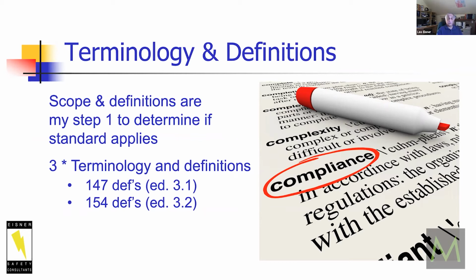But I always go to the scope and I read it and try to understand, does my product fit in the scope of the standard? ISO makes it hard because you can't tell a definition from any other word, because they're all in small letters. There's no small caps. IEC, at least in the 601 series, has small cap letters for defined terms. In third edition amendment 1, there's 147 definitions. Drive you nuts. Well, in third edition amendment 2, we made it worse. There's 154.